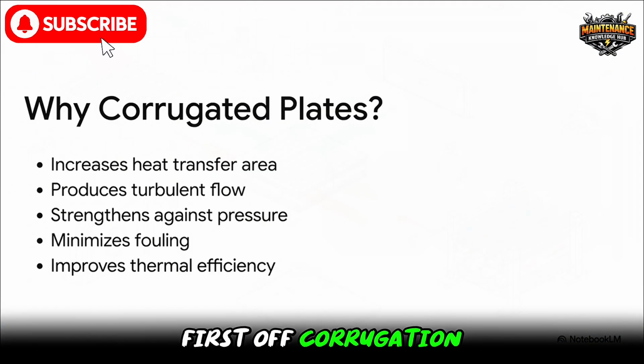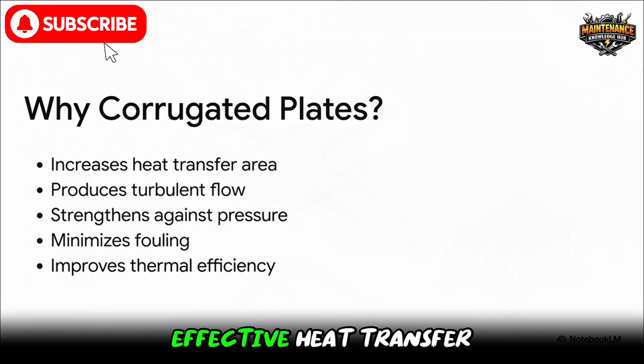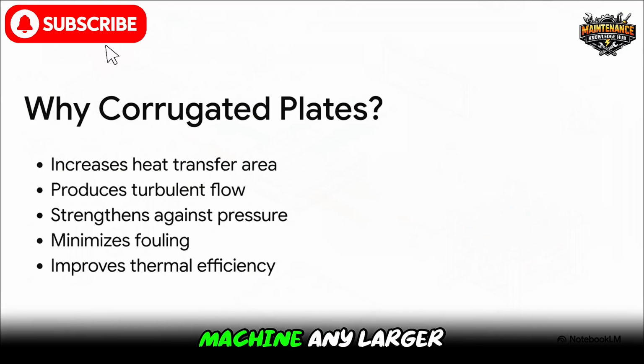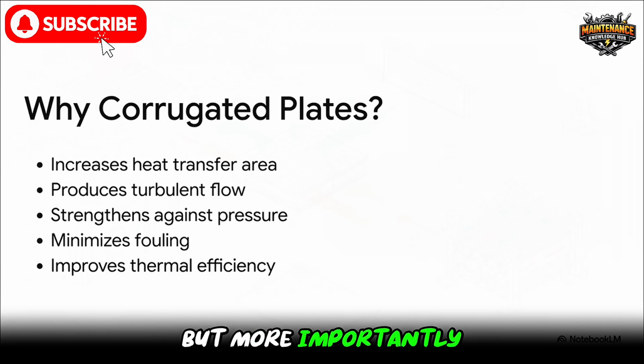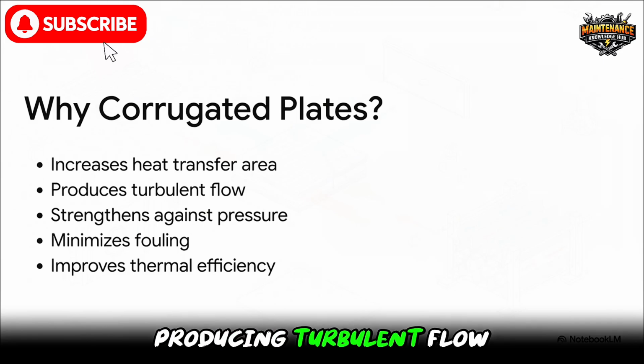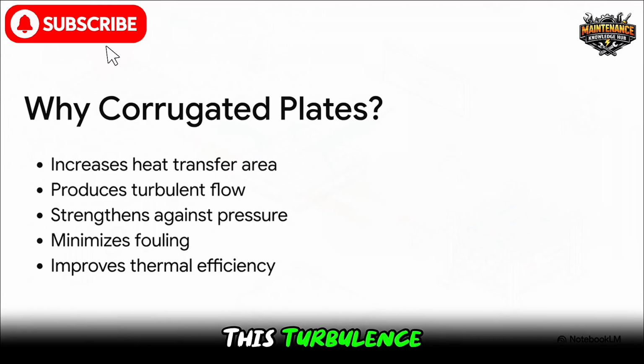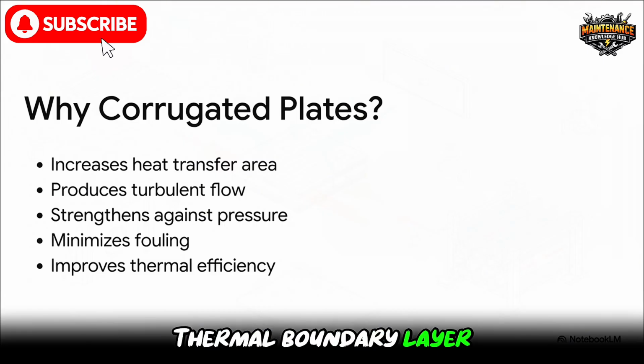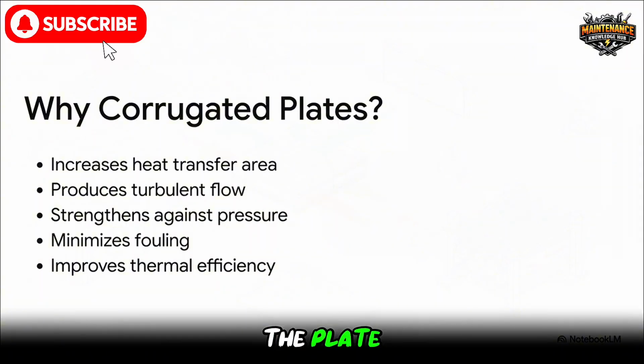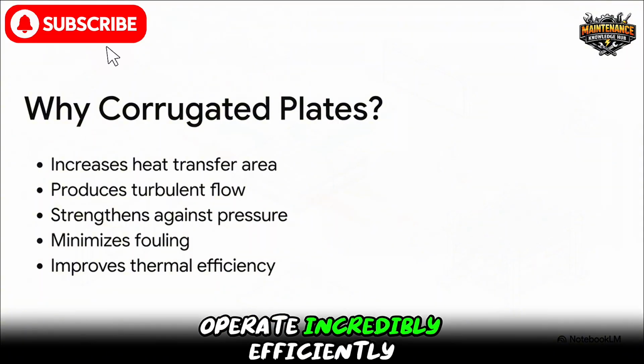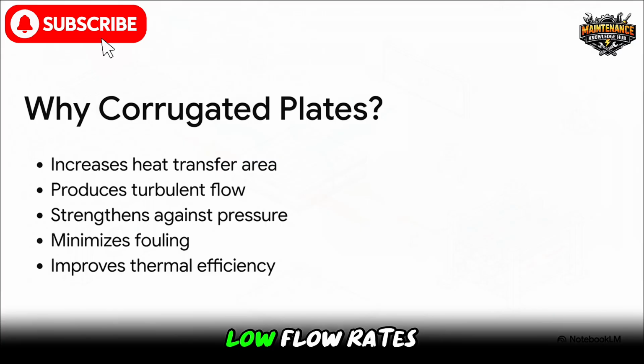First off, corrugation drastically increases the effective heat transfer area without making the machine any larger. But more importantly, it forces the fluid to aggressively bounce around, producing turbulent flow. This turbulence literally breaks the thermal boundary layer, preventing a stagnant layer of fluid from insulating the plate. This allows the machine to operate incredibly efficiently even at relatively low flow rates.